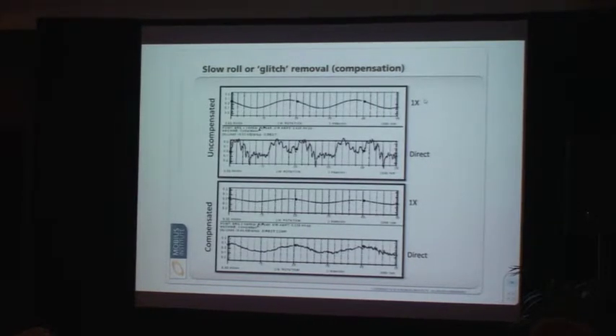Then you can do a couple of things with that: use it as a vector or as a whole recording. Basically, from now on, when we record from this machine, we subtract that out, because that's all the glitches. We remove that from the signal that we're ultimately going to use to analyse, and that cleans things up. That's sometimes called glitch removal or slow roll compensation, possibly other names too. So when you look at one of these graphs, you'll see, has it been compensated?